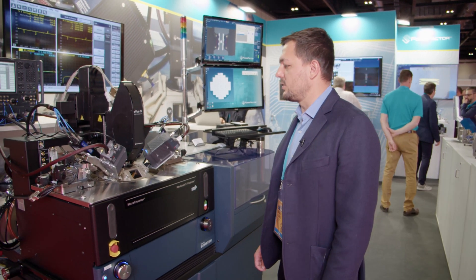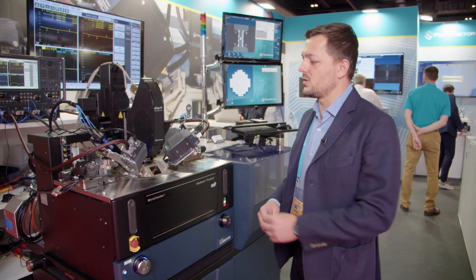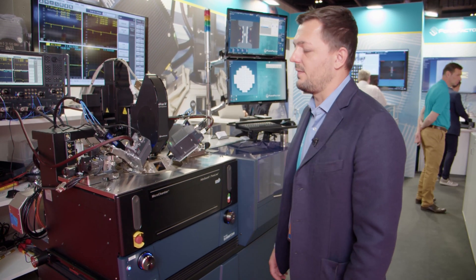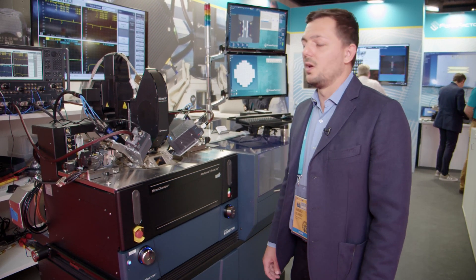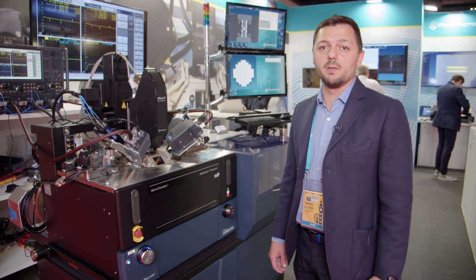This is a fully automated station, with capability to do automated RF measurements using these programmable RPP 504 positioners. Our customers can monitor the calibration and recalibrate without operator intervention. Now our expert Gavin Fisher, our application engineer at FormFactor, will give you an overview of how we can perform a calibration with a single sweep broadband from 10 megahertz all the way up to 220 gigahertz.